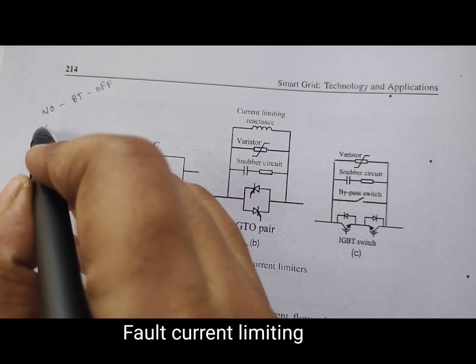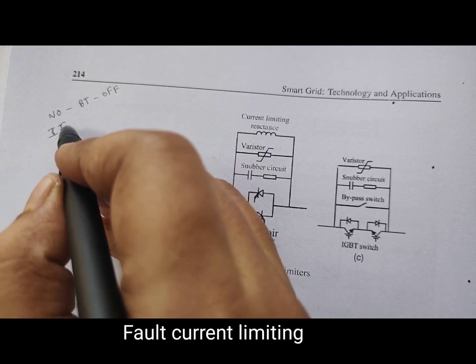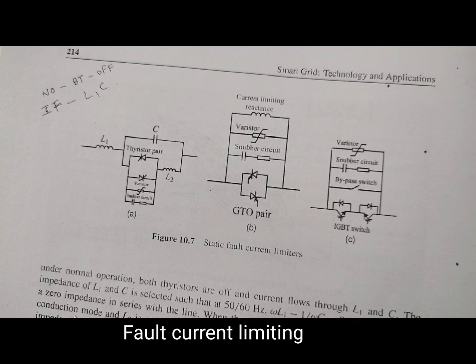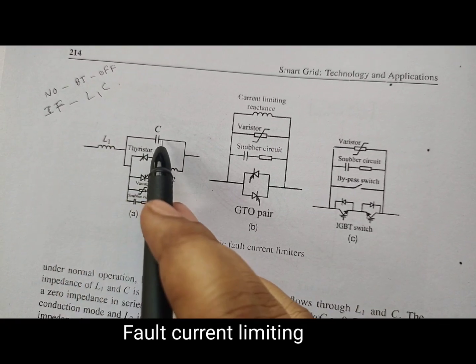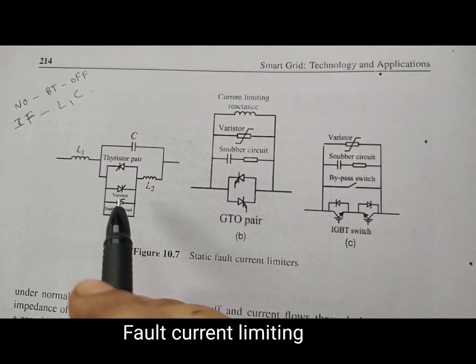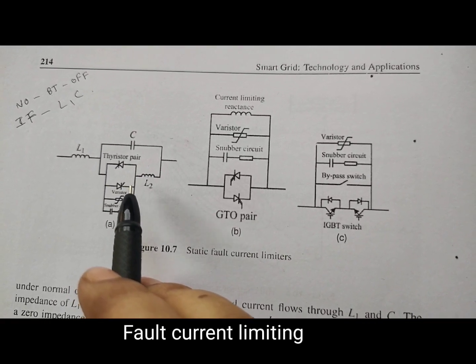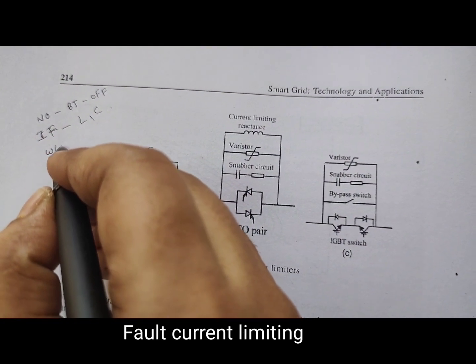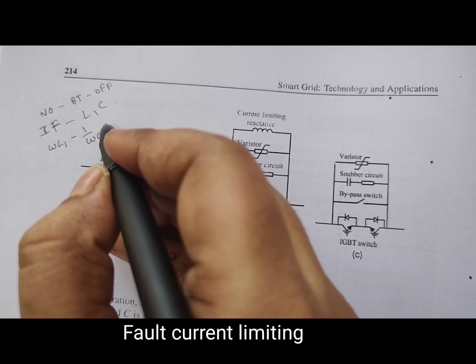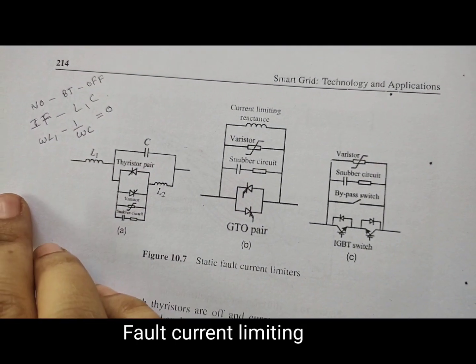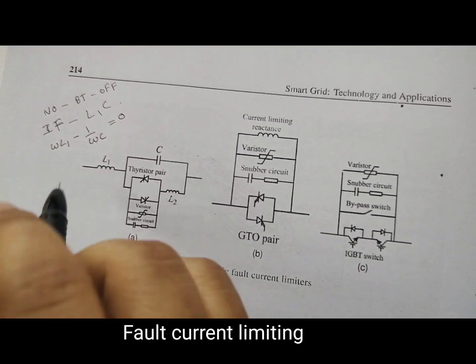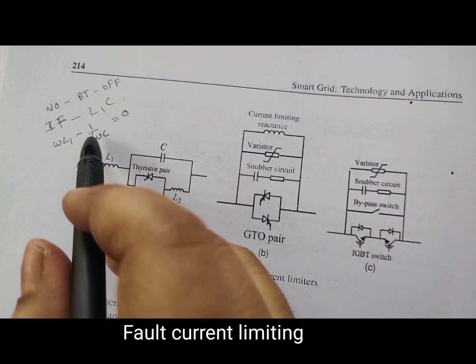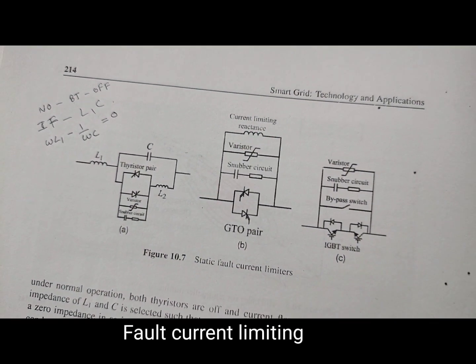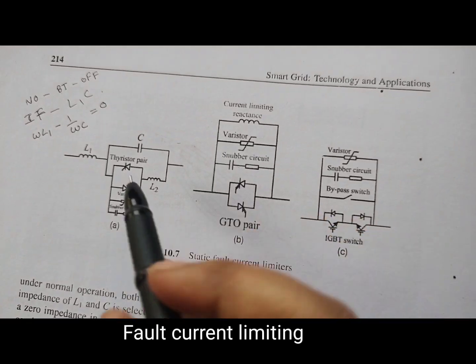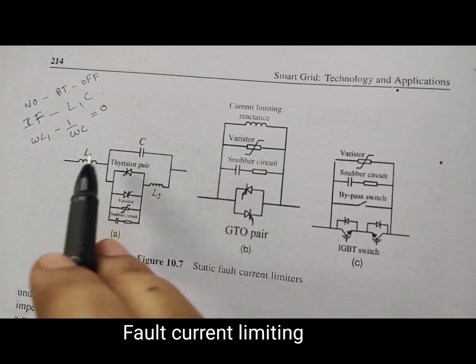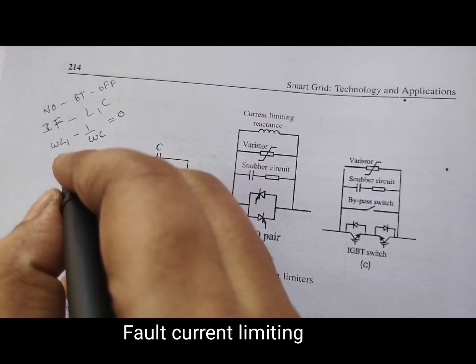Current flows through L1 and C, and the impedance of L1 and C is selected such that at 50/60 Hertz, omega L1 minus 1 divided by omega C equals 0.